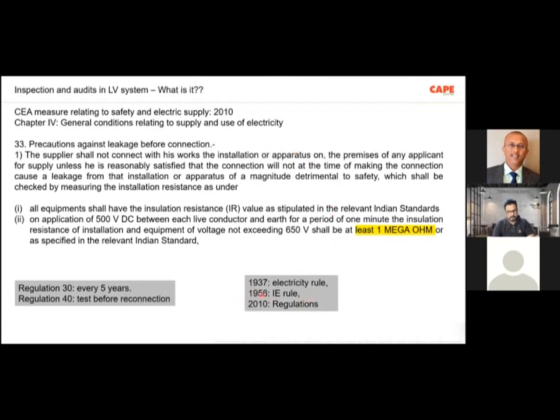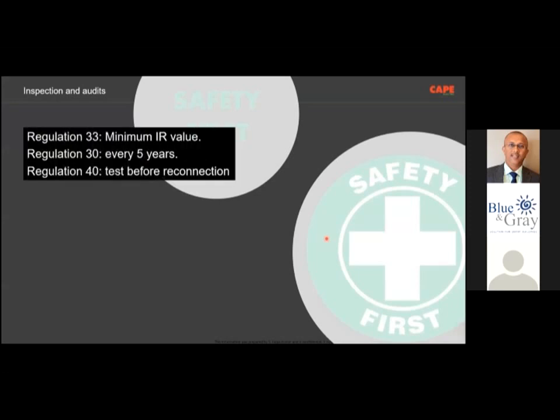And sometimes people ask why this is not updated so far. Of course, writing the entire testing and audits in the regulation will run several pages. There are other documents available. The regulation 12.2 says you should refer to anything more than this for achieving safety. You should refer to the code of practices by the Government of India. So, in order to achieve safety, the first point is you must measure the insulation resistance value. This is the bare minimum requirement to ensure safety. You should do it every 5 years.